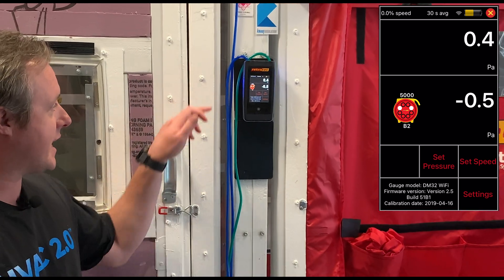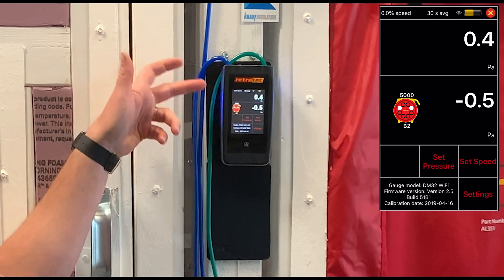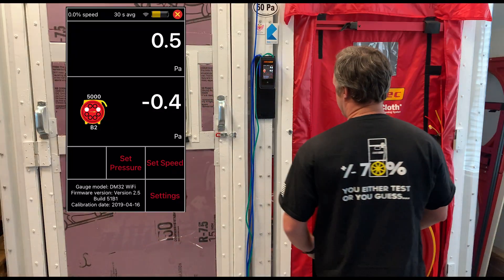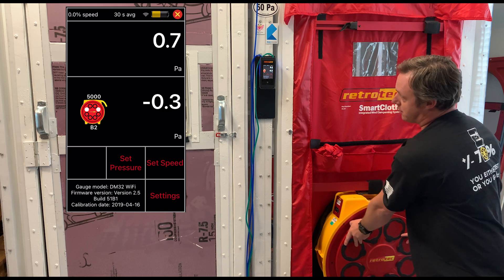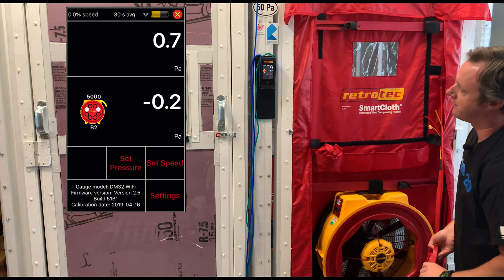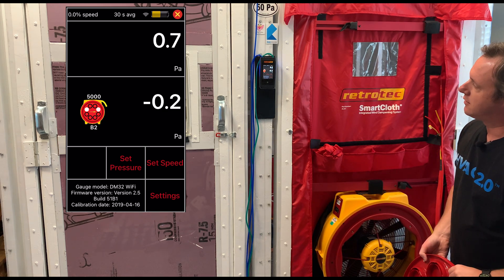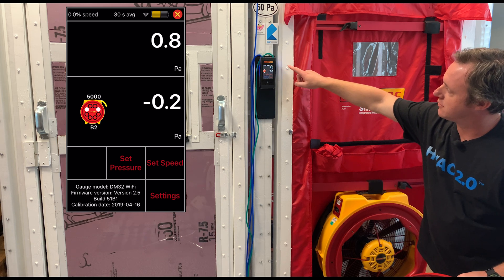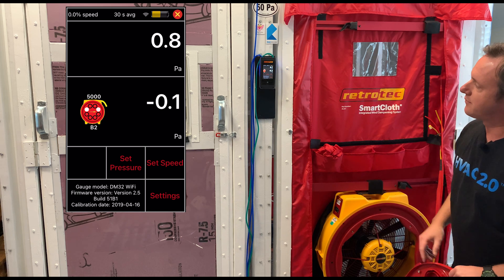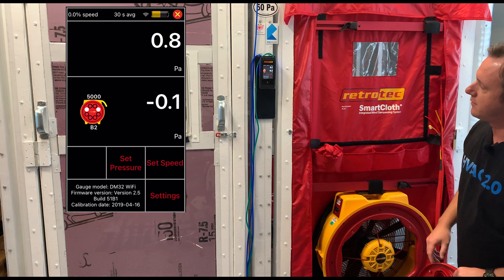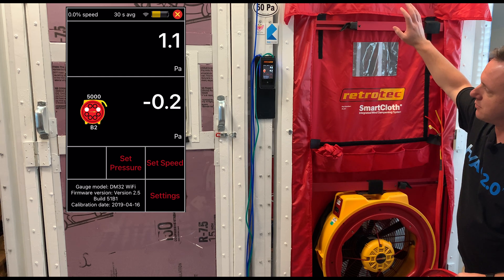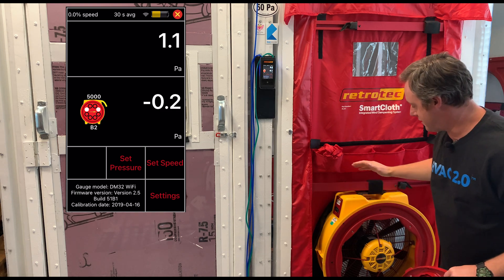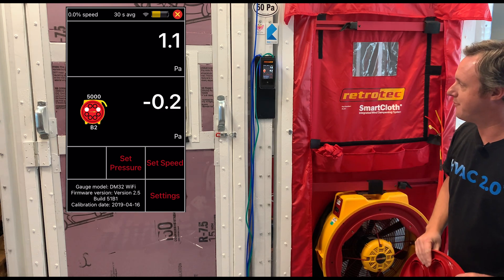Currently we have negative 0.5 Pascals at the bottom and 0.4 at the top. But if I create a larger hole by taking this blower door plate off, we can watch channel B reduce and channel A increase — sending all that pressure towards the top, thus indicating that all of our leakage is at the bottom, as we can see here.